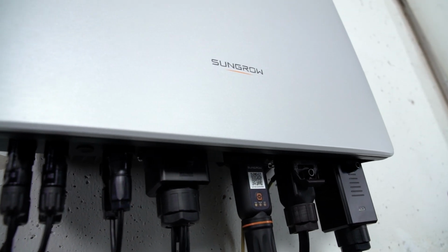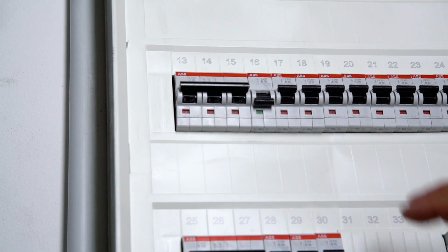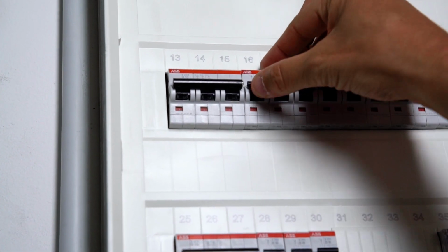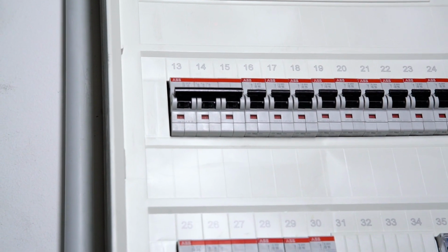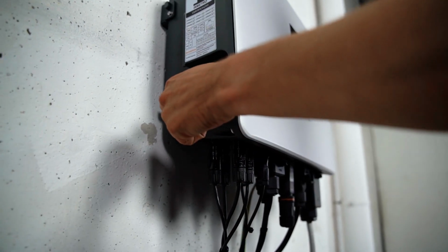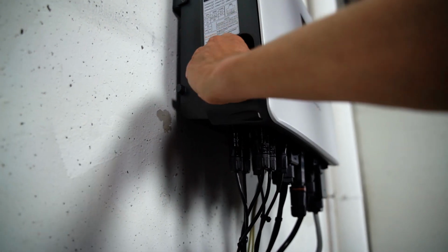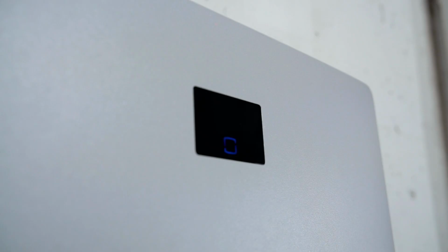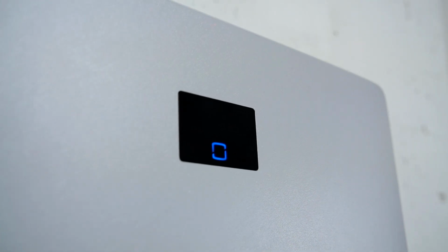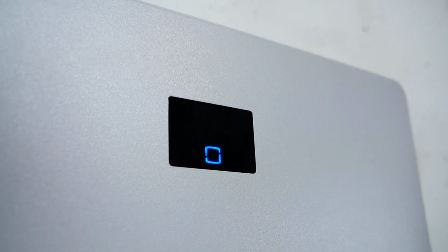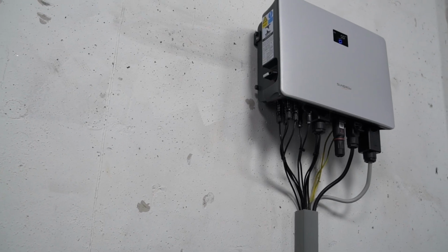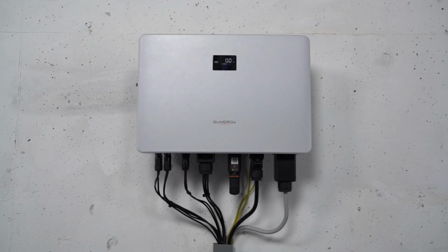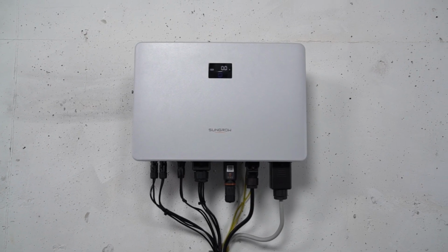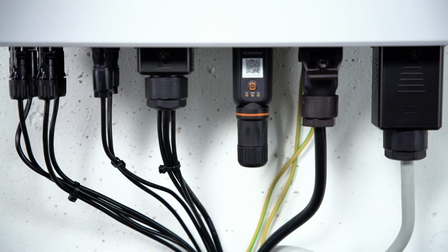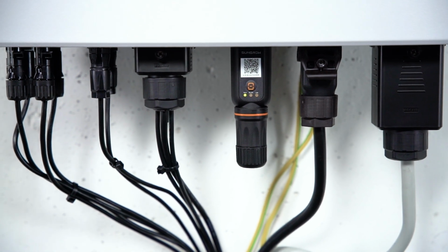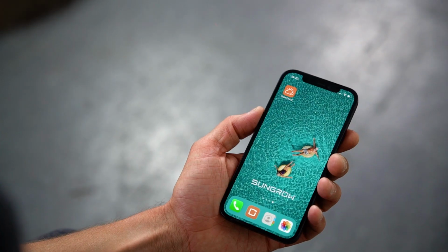Now it's time for commissioning. First, you have to switch on the AC circuit breaker. Next, you have to set the DC switch of the inverter to the on position to connect the inverter to the PV generator. A look at the LED light tells you if everything works properly. If the light shines continuously blue, the inverter is ready for use. If this is not the case, please refer to the manual where you will find a breakdown of the different light signals. When connected, the WiNet module takes some minutes to fully boot.